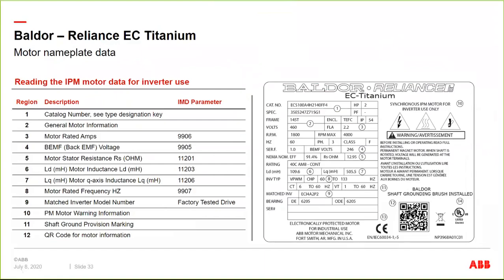Again, I said if you're going to run the motor only on another drive, it has to be a permanent magnet controller, but then it also has to have the accessibility to put in some specific parameters. So in our experience, a standard ID run is supposed to calculate these values. It doesn't really do it well enough. And so we give you the information. We would recommend you manually set these up in a standalone drive. And those are like stator resistance, two values of inductance of the magnetic fields, LD and LQ, back EMF voltage, and rated amps and frequency. So you have to put all these values in. That's really what an ID run would normally calculate anyway, and we just give them to you and suggest you manually put them in. And that's why we have the more detailed nameplate on them.